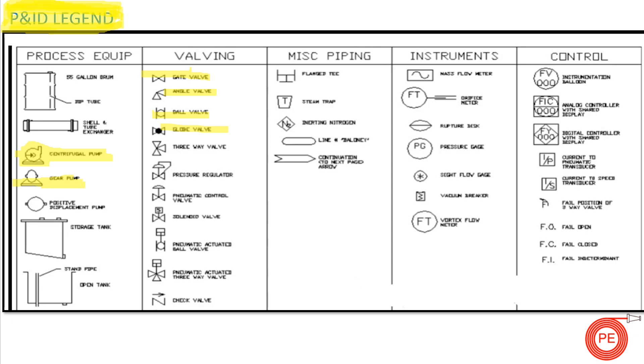You can also see valves: this is the symbol of a gate valve, this is your angle valve, ball valve, and globe valve. All the valves in P&IDs prepared using this legend will capture these symbols, and a person can easily understand what sort of valve or equipment is shown. Similarly, these are symbols for miscellaneous piping and instruments — FT is shown here, your pressure gauge is shown here, your vortex-type flow transmitter is shown — and controls and logics are also shown, including the fail-to-open and fail-to-close categories for valve failure modes.